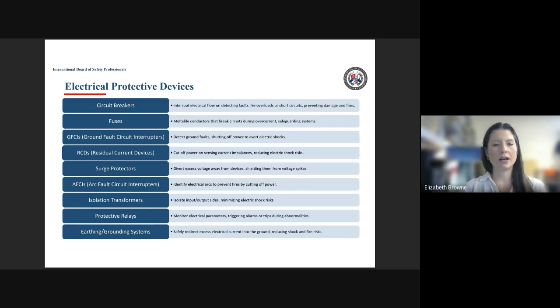We also have overcurrent protection. So we have ground fault circuit interrupters. It detects a ground fault and shuts off the power to avert electrical shocks to employees. I think these are able to do this within 1/40th of a second of detecting a ground fault. So that's a fault for that circuit going to the ground. OSHA requires that we have electrical outlets on ground fault circuit interrupters anywhere we have outlets within 3 feet of a water source.